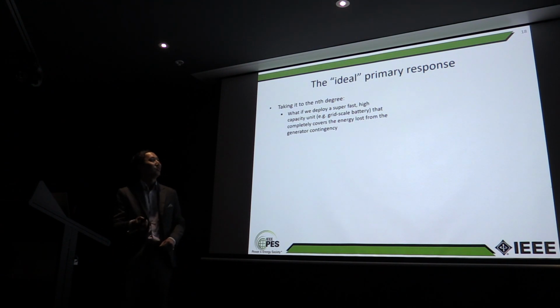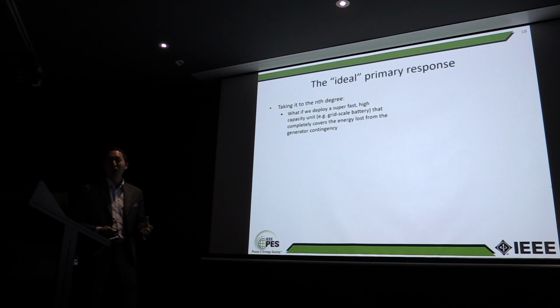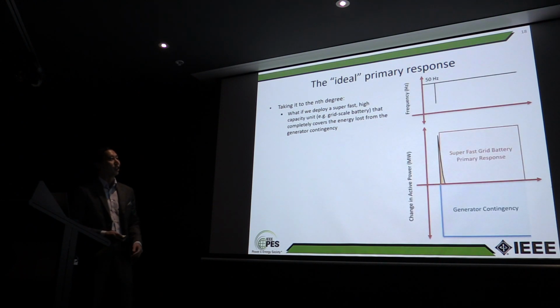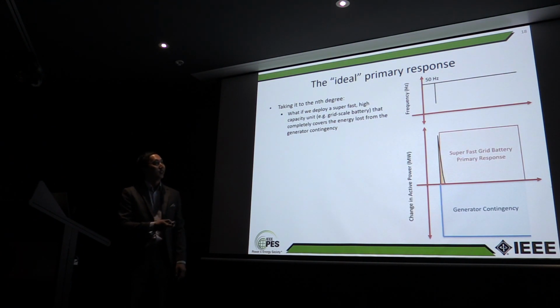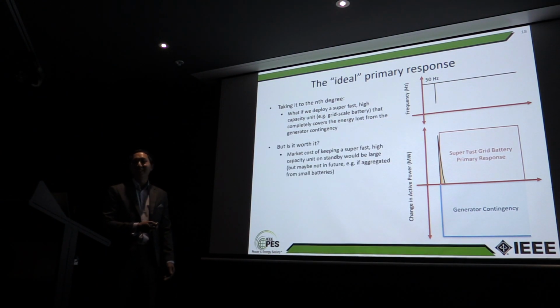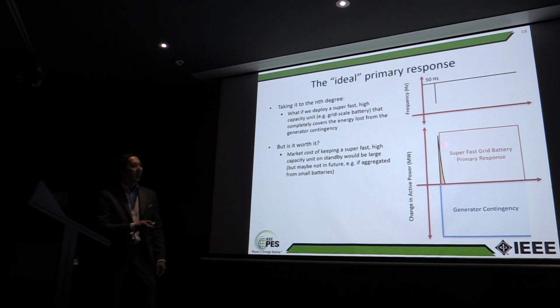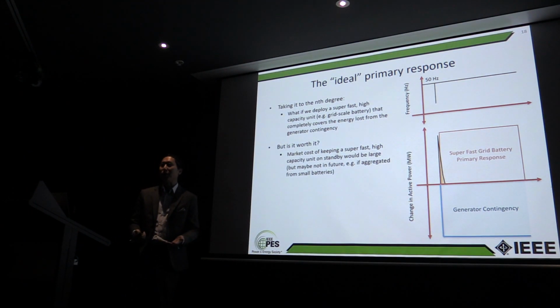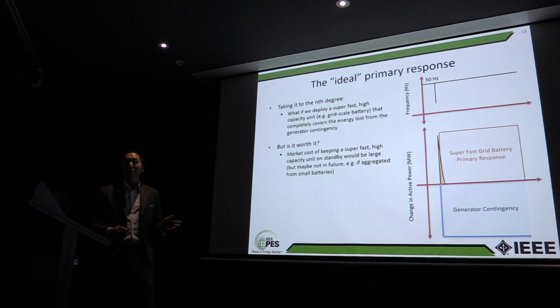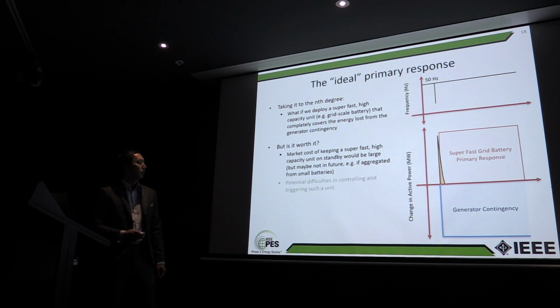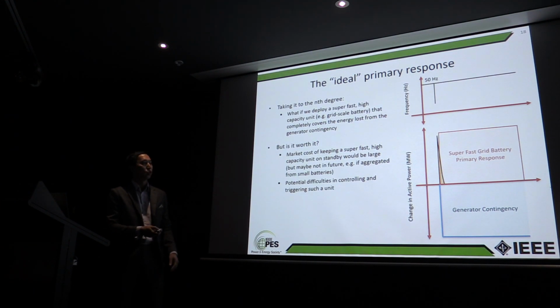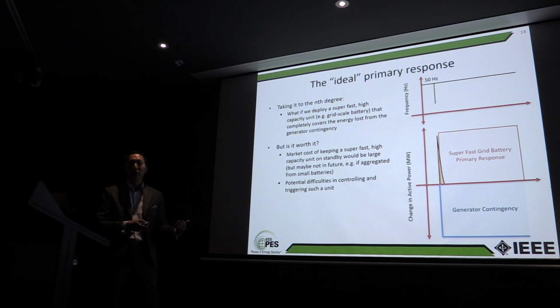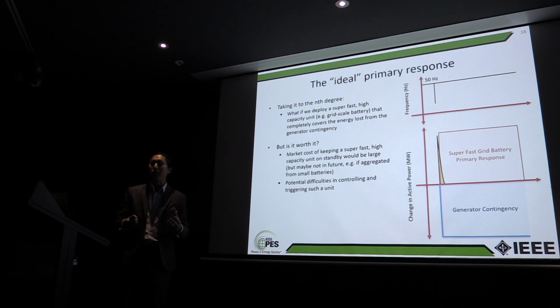So we take it to the nth degree. What happens if we went, you know what, let's put a really fast, really high capacity unit, like a massive battery that completely covers the energy lost. Let's do that, right? See what happens. What you would expect is just a very sharp, transient dip down, and then frequency is just maintained very nicely. Now, you might be asking, is this worth it? Because in order to do this, we would need to have something like this on standby. And the market cost of keeping something like that on standby, I imagine it'd be pretty expensive. But maybe not in the future, if you could aggregate this from small batteries. I don't know. There's also some potential difficulties in controlling and triggering. How do you control something like this to operate at the right level and the right speed and so forth? I think GE's got some ideas on how they would do it.